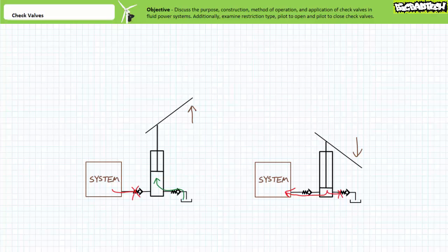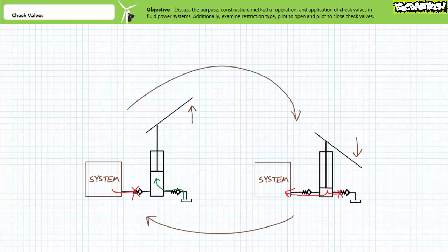The inlet check valve closes during the downward stroke since the pressurized cylinder forces it closed. An operator continues to manually provide pressurized flow to the system with repeated upward and downward strokes of the manual pump handle. An upward stroke sucks in fluid through the open inlet check valve and the outlet check valve remains closed. A downward stroke pushes fluid out of the open outlet check valve and the inlet check valve remains closed.